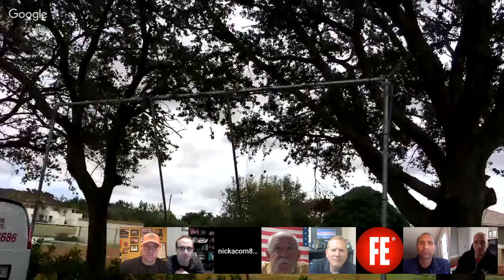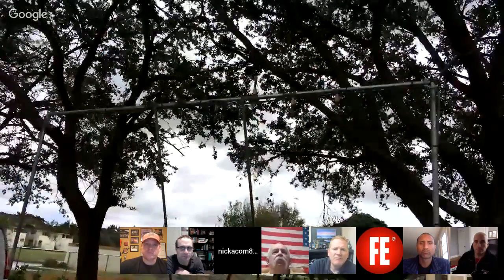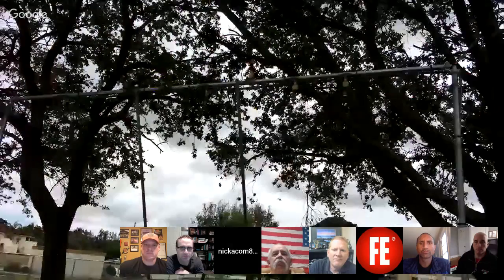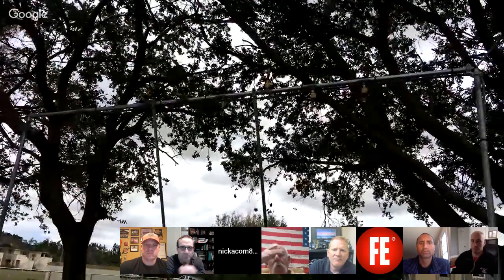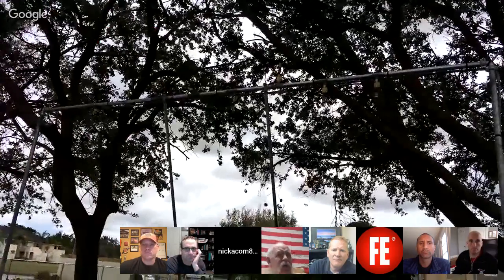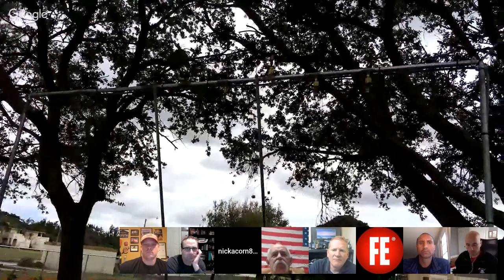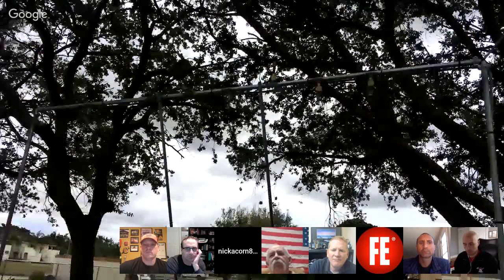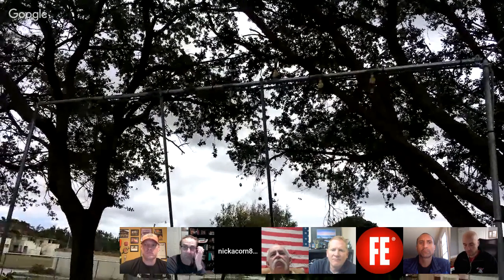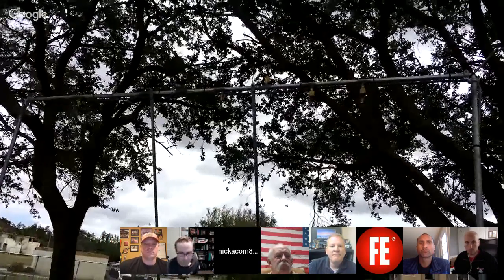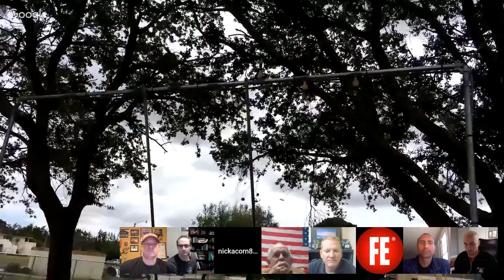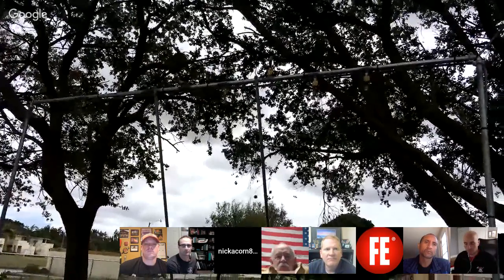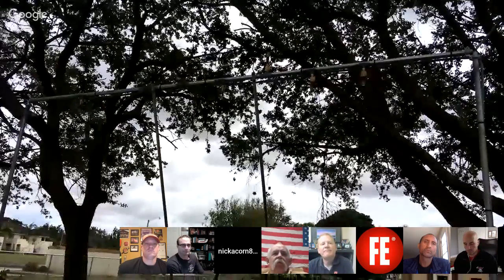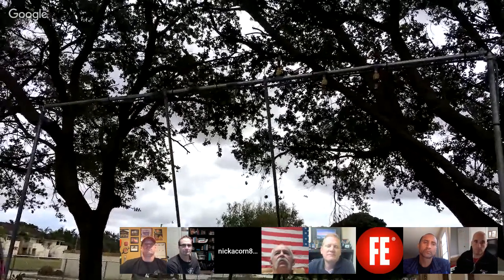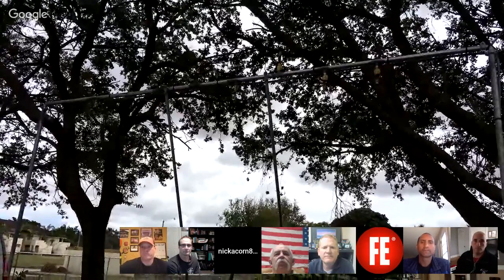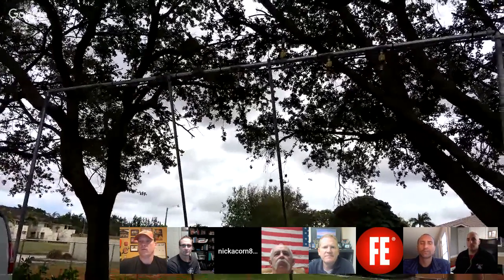The next head is a K25, it's an ESFR sprinkler head in the upright position. The K17, which would be your next sprinkler head, that solenoid valve's dripping a little bit. We're using it outside of its application. And then the last head is an ESFR, what is it, a 28. So that's the big daddy. The ESFRs, now if I remember right, that was the one you were telling me that in the proper application and design, you can use those overhead in lieu of in-rack sprinklers? Absolutely. They're specifically listed heads and eliminate the liability of in-rack fire sprinklers. You keep talking about the forklift, and that's exactly what happens. They hit the heads in the rack. Yep. A much better application.